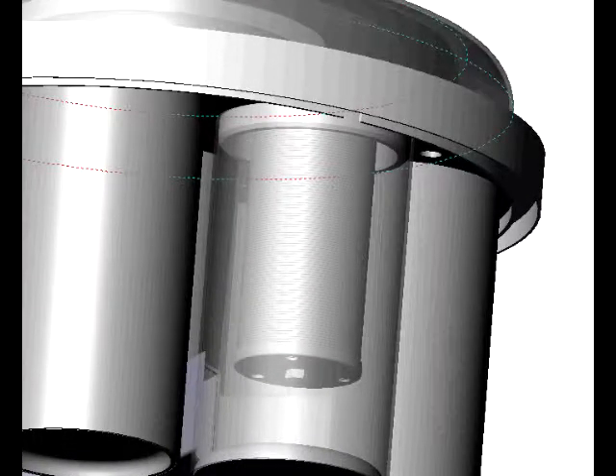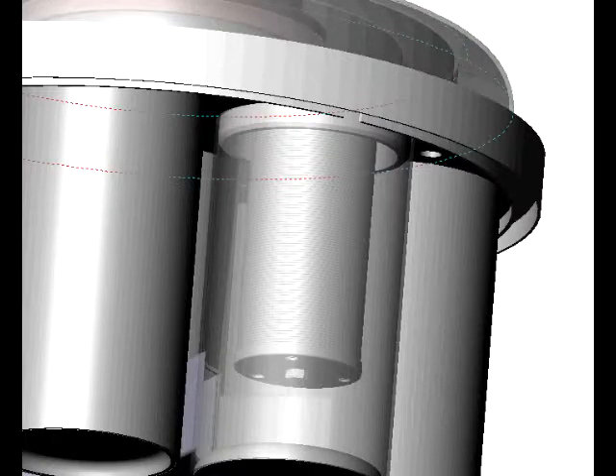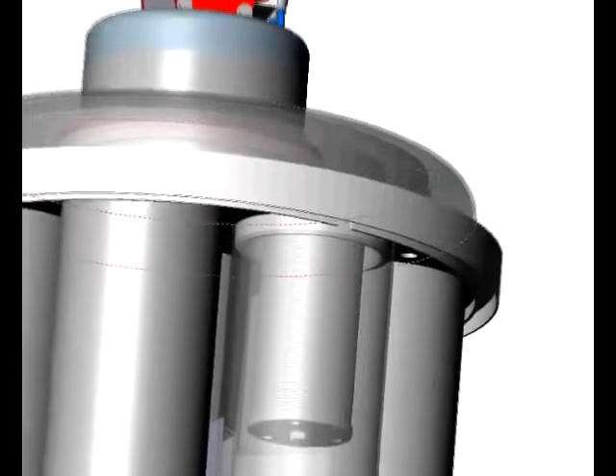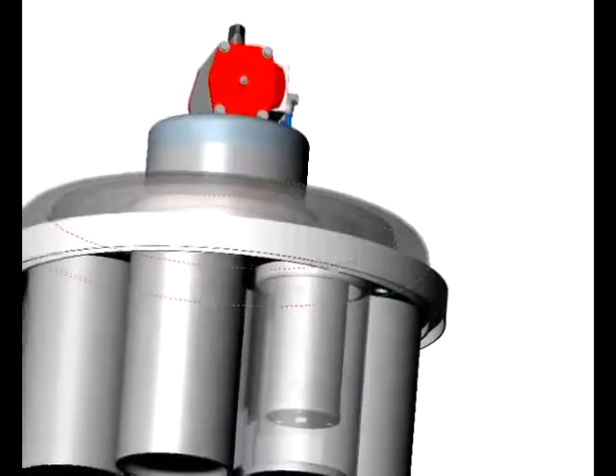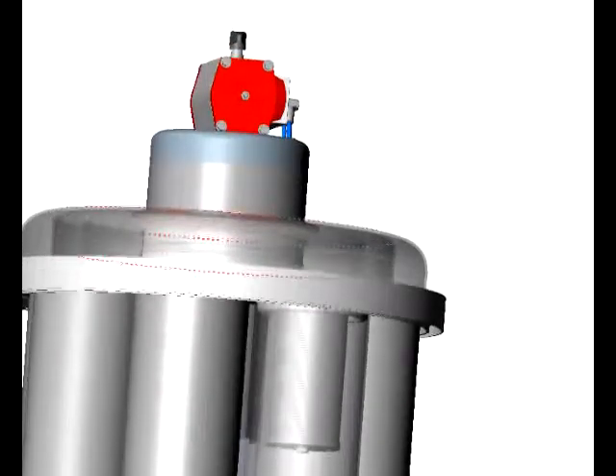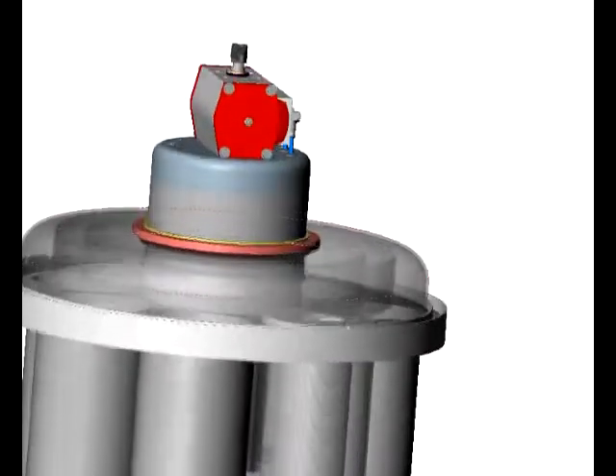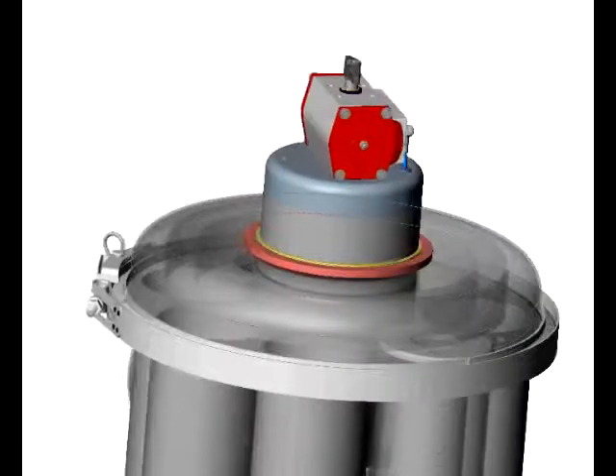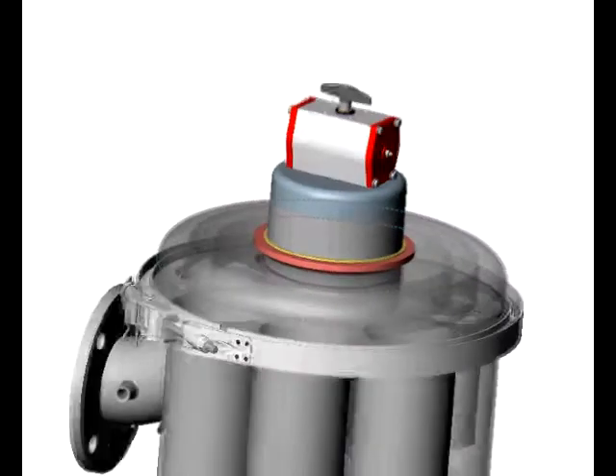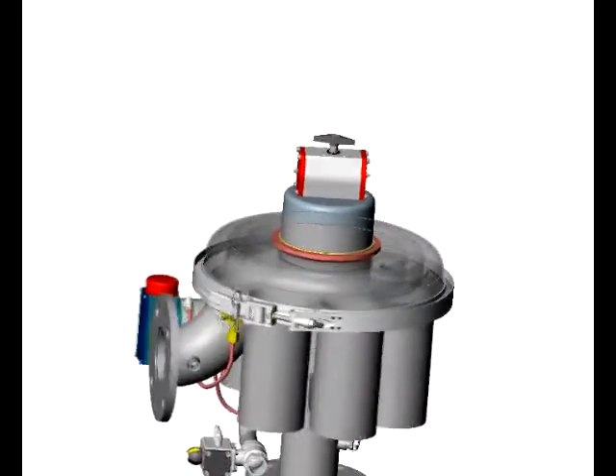Any debris which is larger than the micron rating of the element remains on the outside. The cleaned fluid now passes through the filter element and up into the donut cover where it joins with the flow from the other five elements. This common filtered fluid exits the filter via the discharge elbow and flange.